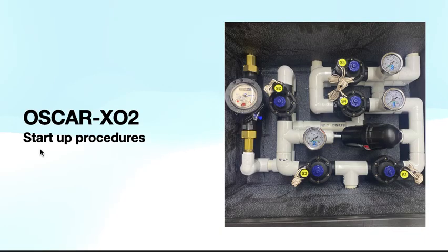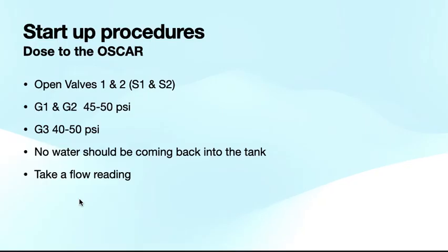And again, just to note, every reverse flush headworks is going to have 3 pressure gauges, always with the same labels, 1, 2, and 3. They're going to have 5 solenoid valves and a water meter. So this reverse flush headworks is facilitating 3 things that the water is going to be doing. The main thing is water going out to the Oscar drain field. So the pump comes on, goes through the headworks, out to the Oscar coils, and there it stays.